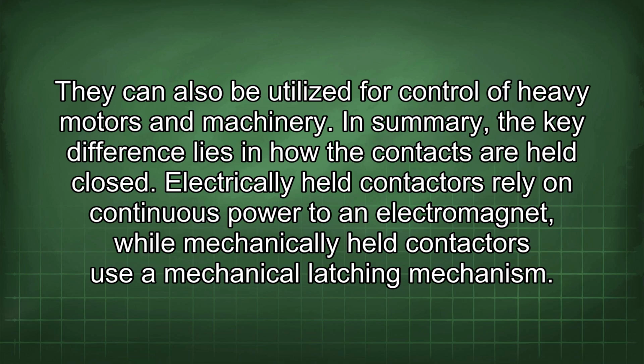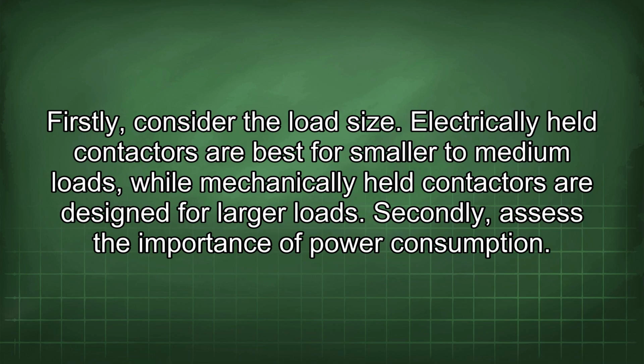In summary, the key difference lies in how the contacts are held closed. Electrically held contactors rely on continuous power to an electromagnet, while mechanically held contactors use a mechanical latching mechanism. Firstly, consider the load size. Electrically held contactors are best for smaller to medium loads, while mechanically held contactors are designed for larger loads.